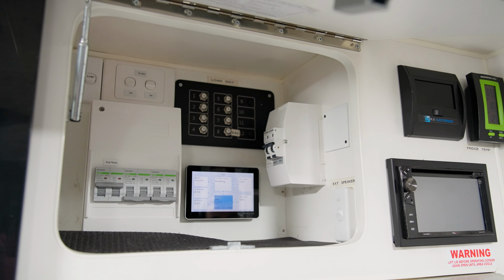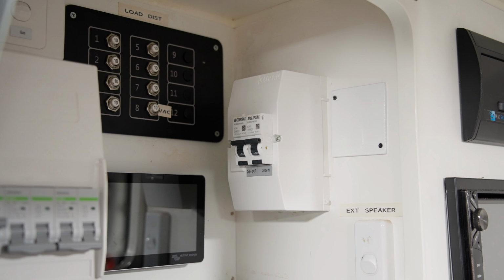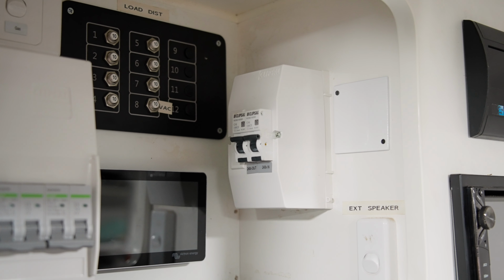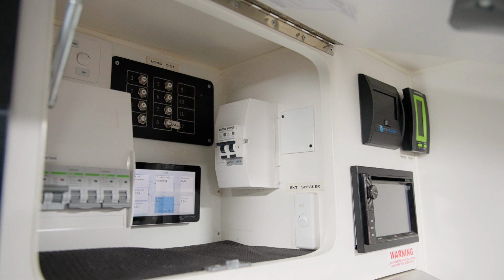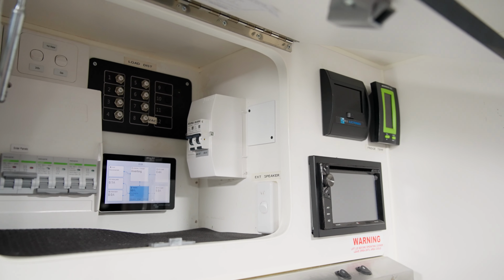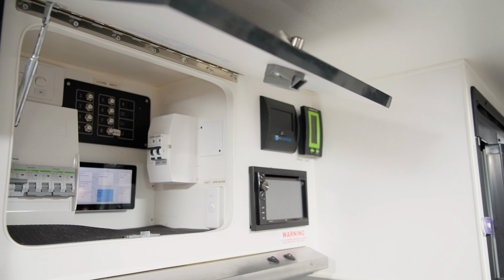Then we've also got new circuit breakers in here - RCDs for the MultiPlus. Same as always, you've got the one for the incoming, so shore power comes in, goes to the RCD, comes out of it, goes to the multi, then power comes back to the other RCD, and then it goes from there to all your GPOs. So we just swapped them out, now you've got 2 new RCDs there.